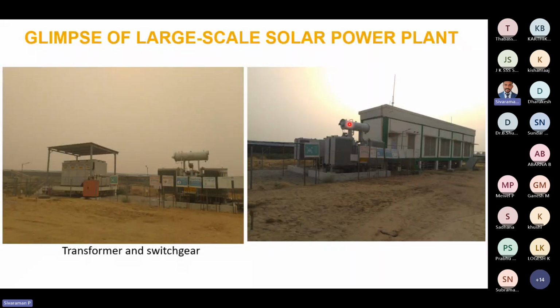Then this will be the transformer. This transformer is called an inverter duty transformer or simply a solar transformer. This transformer is not a typical distribution transformer that we see on the road. It has some additional features required for solar inverter applications, like withstanding harmonics and voltage fluctuations. There are some power quality requirements for solar inverters, so those additional features this transformer has.